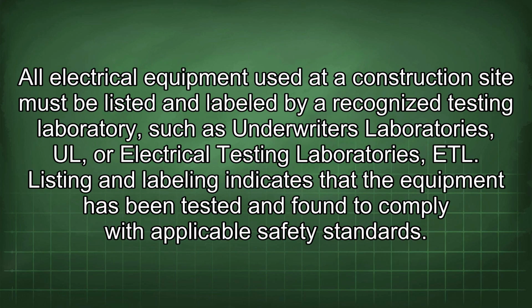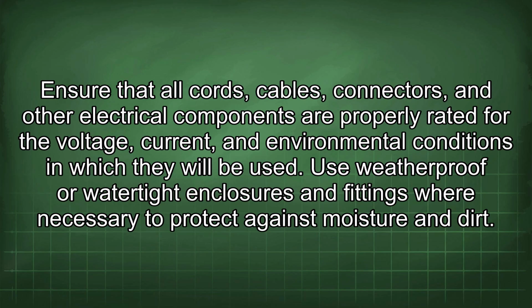All electrical equipment used at a construction site must be listed and labeled by a recognized testing laboratory, such as Underwriters Laboratories, UL, or Electrical Testing Laboratories, ETL. Listing and labeling indicates that the equipment has been tested and found to comply with applicable safety standards. Ensure that all cords, cables, connectors, and other electrical components are properly rated for the voltage, current, and environmental conditions in which they will be used.